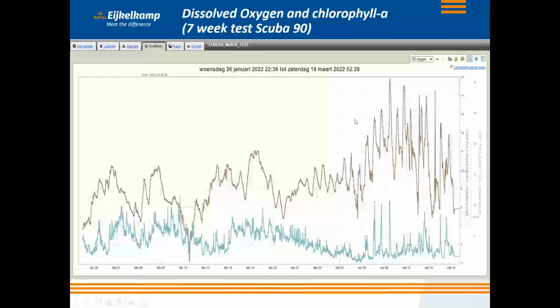When the sun starts shining, the chlorophyll A peaks together with the oxygen concentration line, and that gives us a good indication that the photosynthesis is working well. As you see, still during 7 weeks there's no decline in oxygen because of fouling of the sensor, and that is also a big advance against our former approach from Accurate.